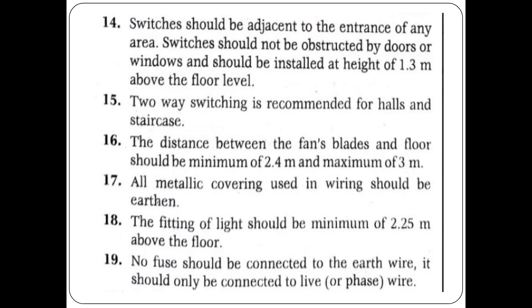Switches should be adjacent to the entrance of any area. Switches should not be obstructed by doors or windows, and should be installed at a height of 1.3 meters above the floor level.